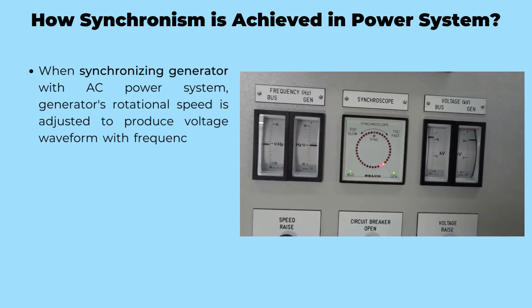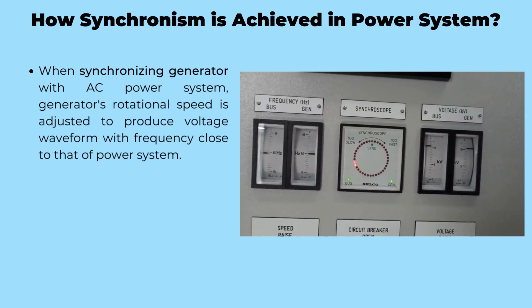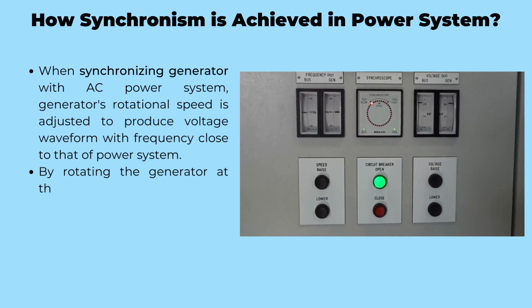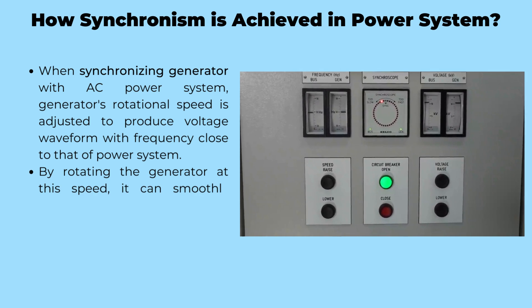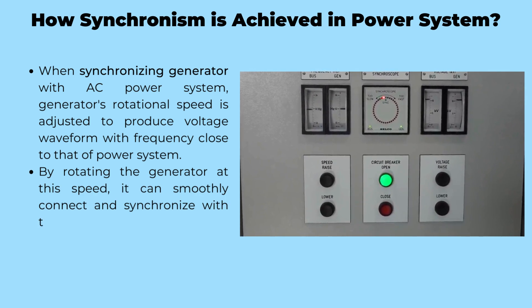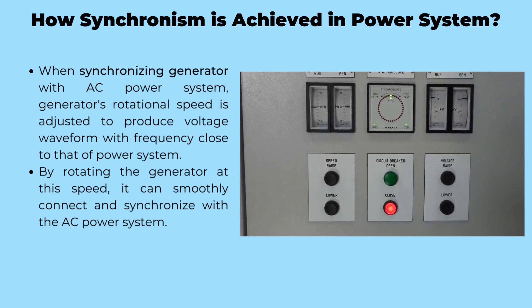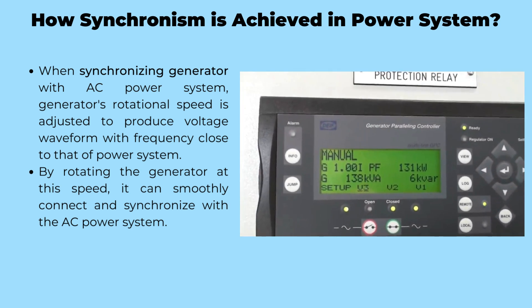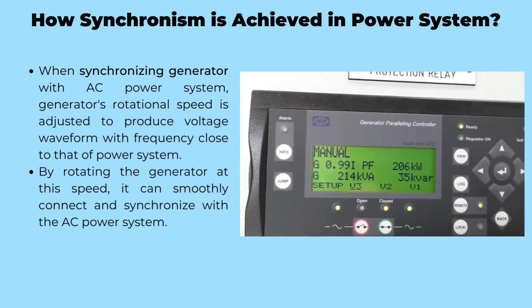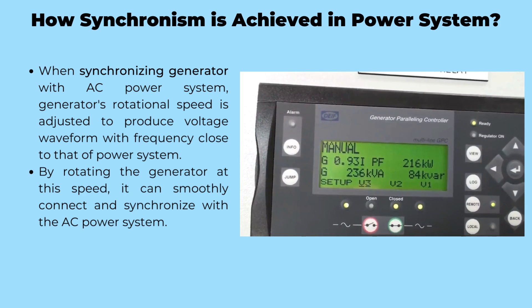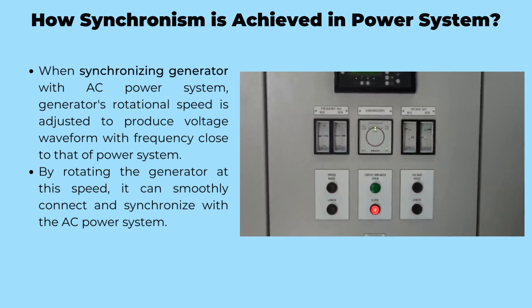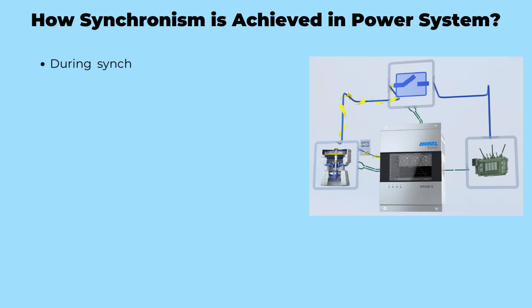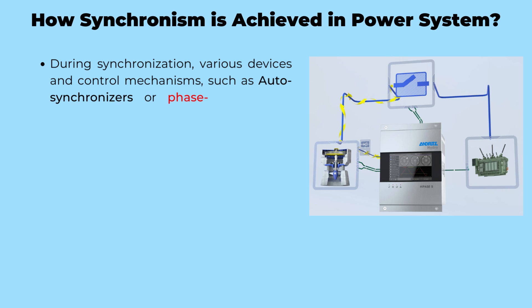This process requires precision and control to achieve smooth and reliable synchronization. Specialized devices called synchronizers come into play, monitoring the voltage and frequency of the generator and comparing them to the corresponding values in the power system. With their guidance, the generator's speed and phase angle can be adjusted gradually, bringing it into perfect harmony with the grid. Once synchronization is achieved, the generator becomes an integral part of the power system. The aim is to align the frequency, phase, and voltage of a generator with the existing power system using specialized devices such as autosynchronizers or phase-locked loops.